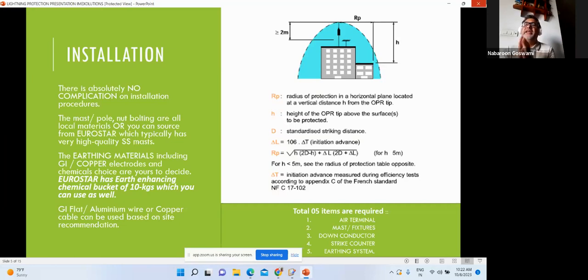You need an external lightning air terminal. It has to be put in a clear area, at least 1.5 to 2 meters above your antenna, just like you'd place your telecom antennas, because when lightning comes and gets attracted to the EMF being created, it wants to get inside the first medium available, on a first come first serve basis. So if your lightning protection system is just above your antenna, it will be the first target, and that's what we want: for the system to attract the lightning and safely ground it.